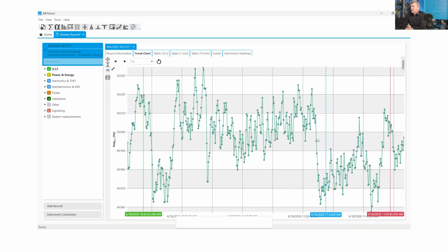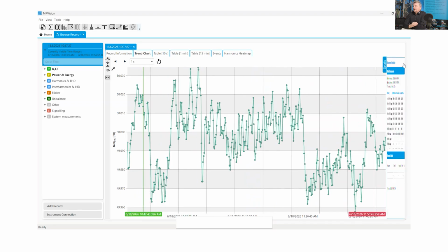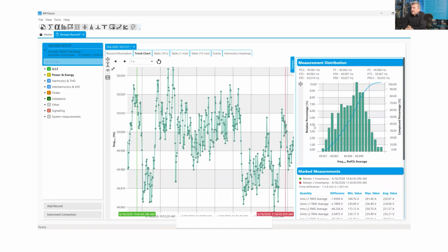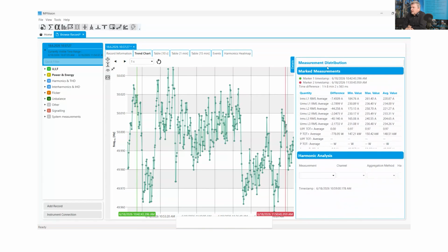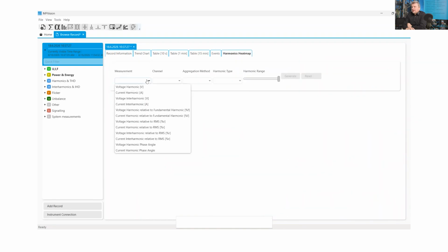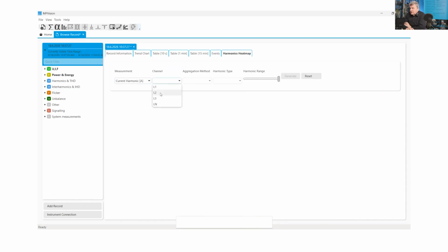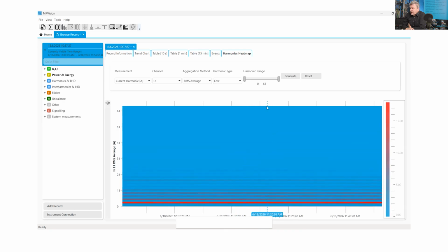Go to a different view, for example, measurement distribution, which is a Gauss distribution of the data, also with the percentile calculation of the data from 0.5 percentile up to 99.5. Then there is specific analysis of the actual data with min, max, and average value. We are also preparing the so-called heat maps, where you can monitor the overview of specific harmonics over the whole recording time. Here we extend this, for example, up to the 16th harmonic component. And you can see that during this period of time, the third harmonic was the most influenced.